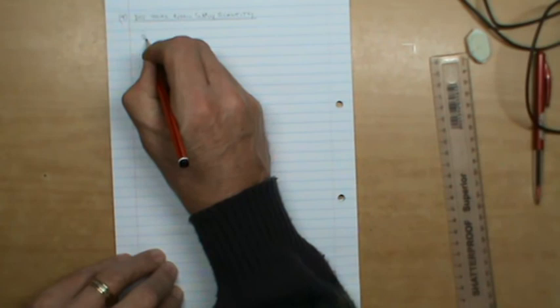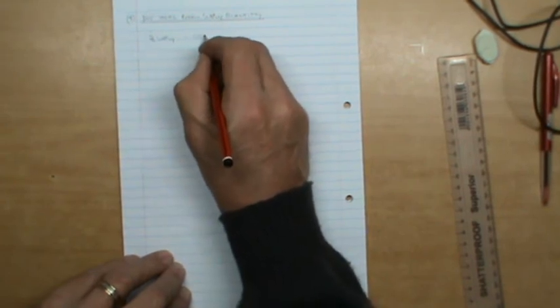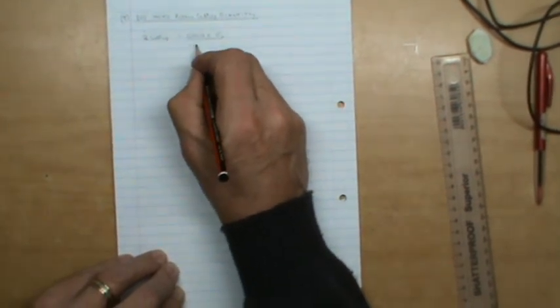But now we've got to know what is the total volume that is going into this room. The only way that we determine that is by saying that the quantity going in, Q supply, is equal to the effective room sensible heat times the specific volume at 4, divided by the specific heat capacity of air times delta T.